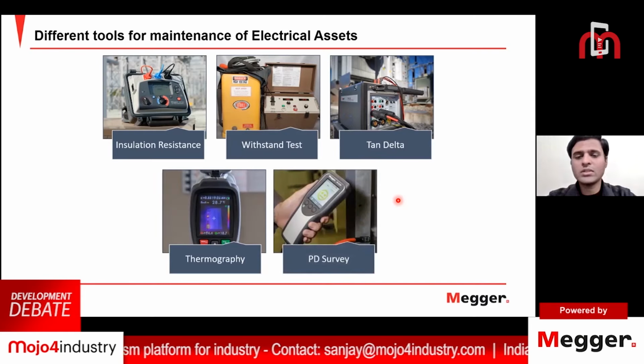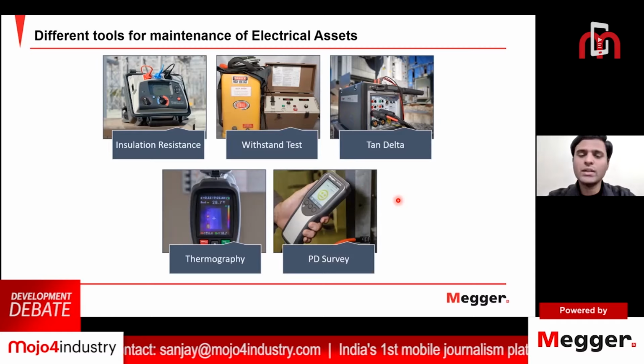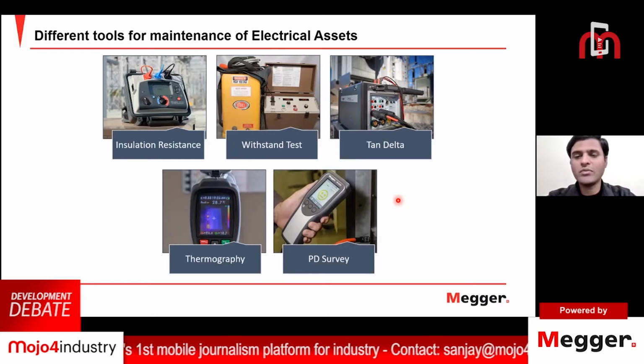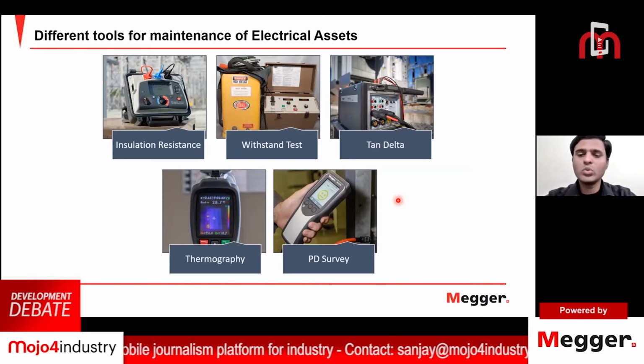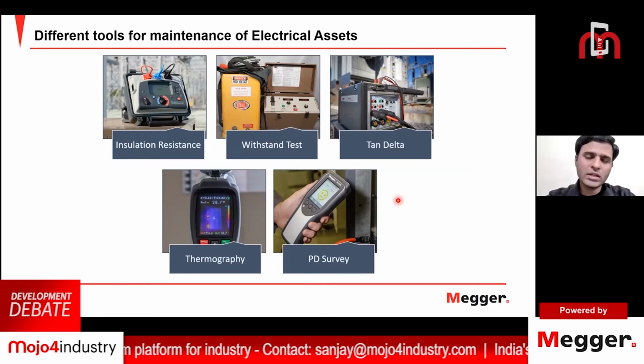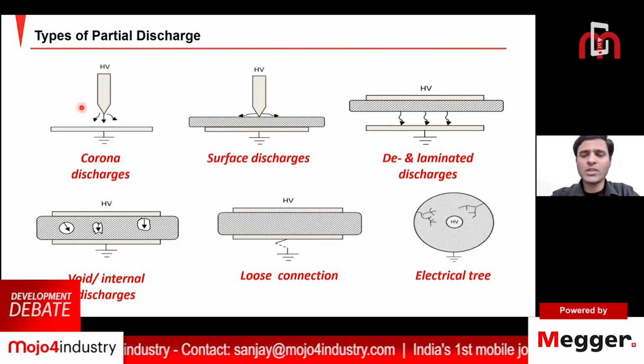So nowadays there is a trend of using partial discharge surveys on electrical assets, which will help you detect some of the discharges in online conditions. From the outside of the panel, you are detecting the different types of discharges emitted from the internal components of your electrical assets, like medium voltage switchgear panels or transformers. So the PD survey is a new tool that came into the market, which is very well accepted, and many industries are looking forward to using this survey tool to do predictive maintenance and understand the condition of the electrical asset. So what are the different types of partial discharges?